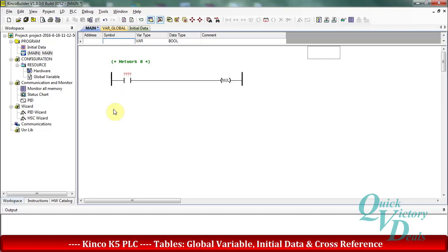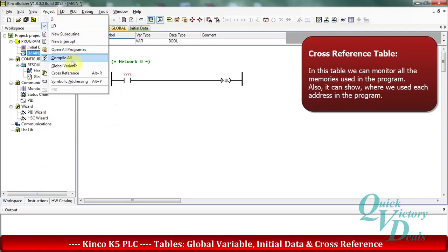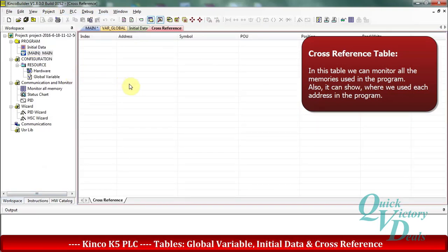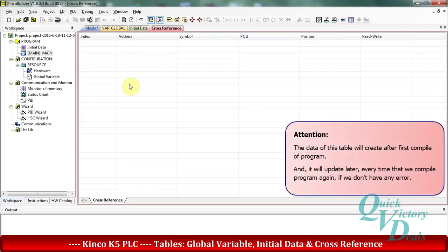In the next part we want to check the cross-reference table. We can go to the workspace area or from the project menu choose cross-reference. In this table we can see all of the memories used in the program — it is very useful when we need to find an address used somewhere in the program and what its symbol is. The data in this table is created after we compile our program, and after each compile, if there are no errors, the table will update.